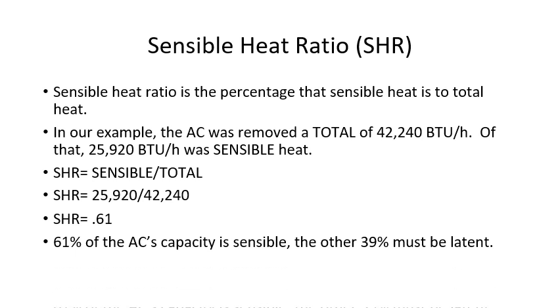What does this tell us? It tells us that 61% of the air conditioning's capacity was sensible, which tells us also that 39% must be latent. If it's not sensible, it has to be latent — there is no other alternative.